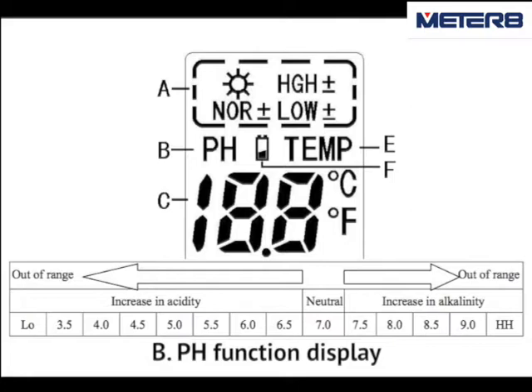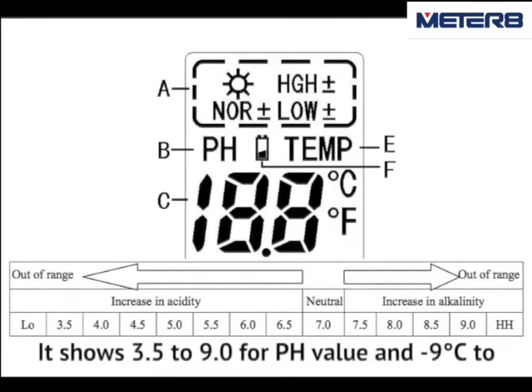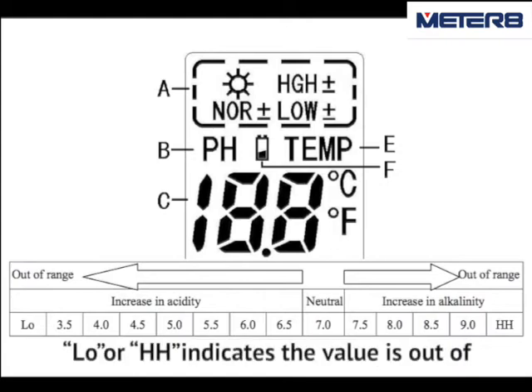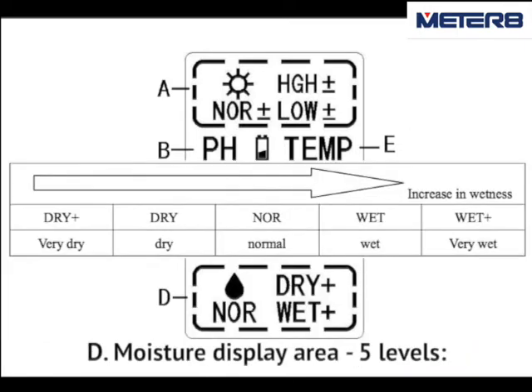B. pH function display. C. pH or temperature value display — it shows 3.5 to 9.0 for pH value, and minus 9 Celsius degrees to plus 50 Celsius degrees for temperature. LO or HH indicates the value is out of measurable range.